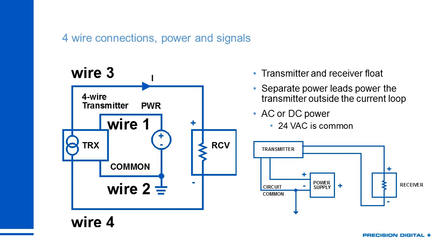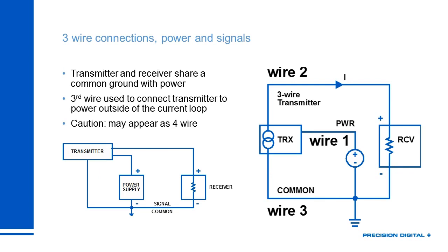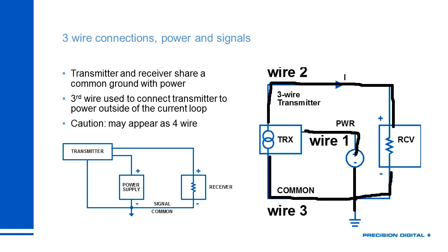A three-wire device is essentially the same as a four-wire device but without isolation. The 4 to 20 milliamp loop is not floating relative to the power supply. A three-wire transmitter has: wire one bringing in power, wire two carrying the 4 to 20 milliamp output to the receiver, and wire three shared between the receiver return and the power supply common — they are literally the same connection. Some three-wire devices have four terminals to make wiring easier, but electrically it's the same node.